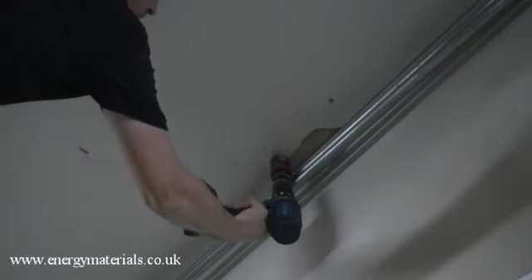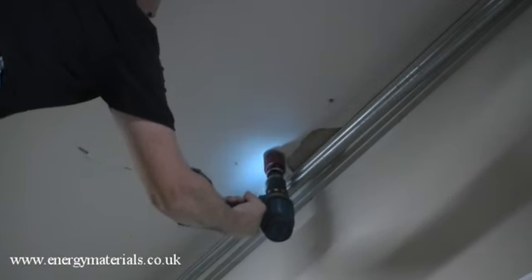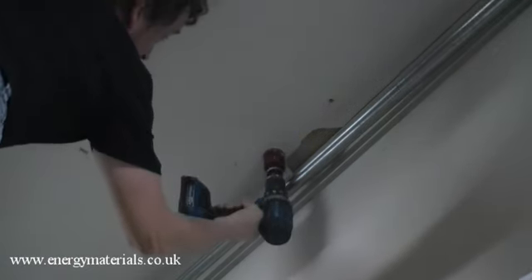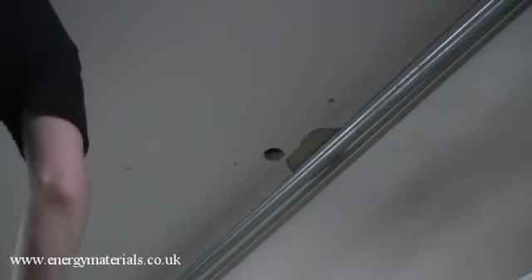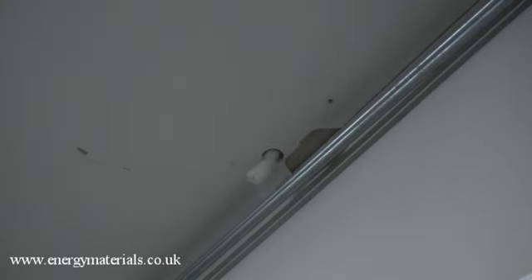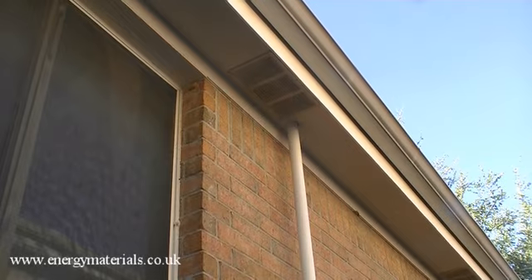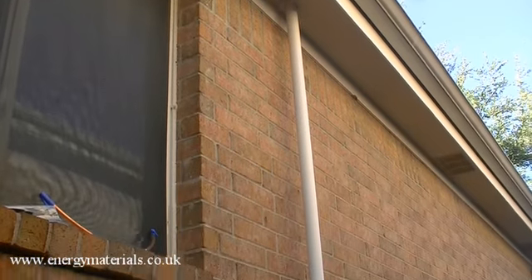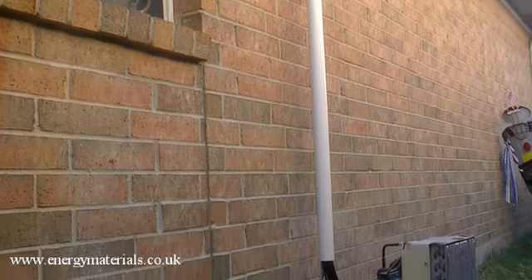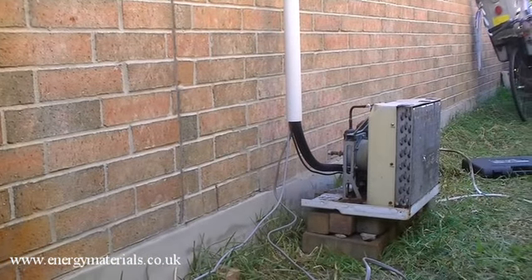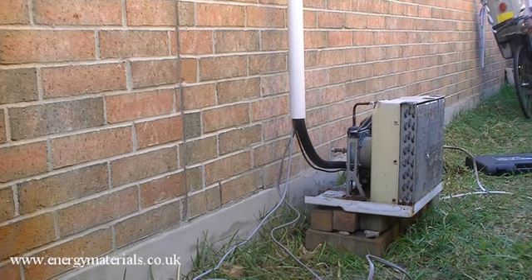Now we install the line set. First off, we drill a hole. That's a big hole. Now we push the line set through the hole where we're going to connect to our AC unit. On the outside of the building, the line set is pushed through a 2-inch PVC pipe. This is a standard drain pipe. This is a lot more cost effective than a traditional outside ductwork for an AC unit.